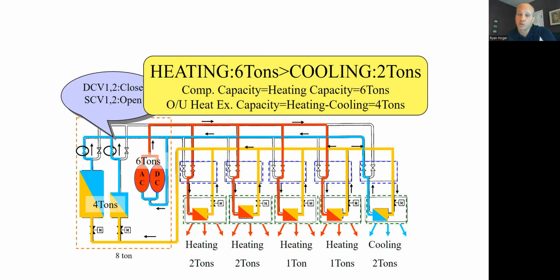Opposite scenario, I've got more heating than cooling in this case. I have 1, 2, 3, 4, 5, 6 tons of heating needed, 2 tons of cooling. The outdoor unit goes into the heating mode, which means the reversing valves flip the other way. In this case, it's going to be picking up 4 tons of heat from outside. It's going to pick up 2 tons of heat from zone number 5, and it's going to run all those through the compressor and send it into these 4 zones. So I'm going to get 1, 2, 3, 4, 5, 6, 7, 8 tons of heating and cooling combined capacity for the compressor horsepower operating price of 6 tons, for the heat rejection fan, outdoor fan price of 4 tons.